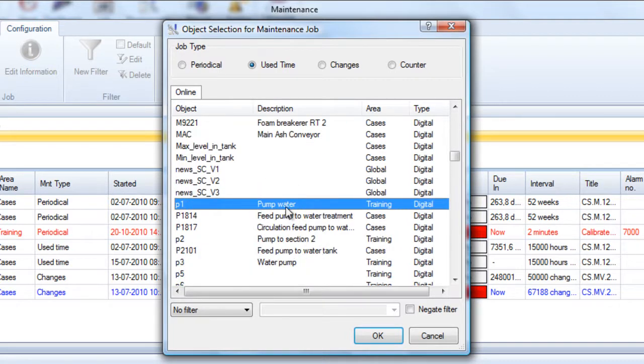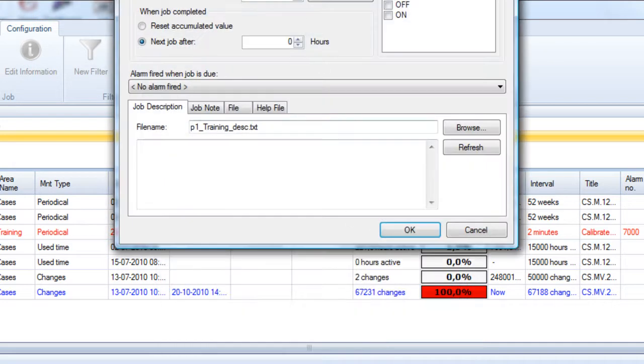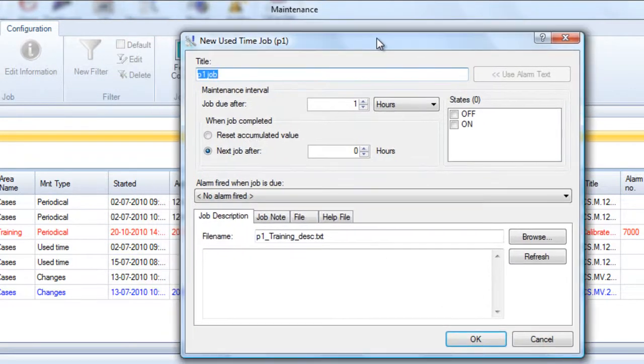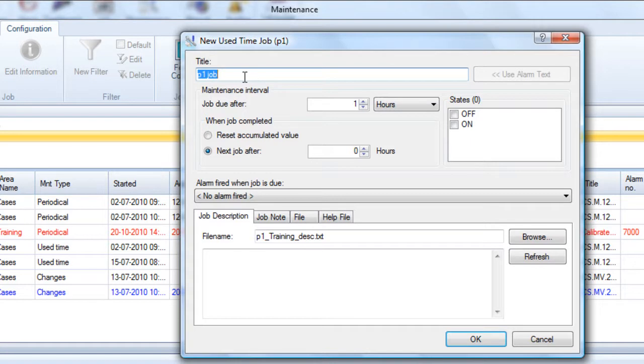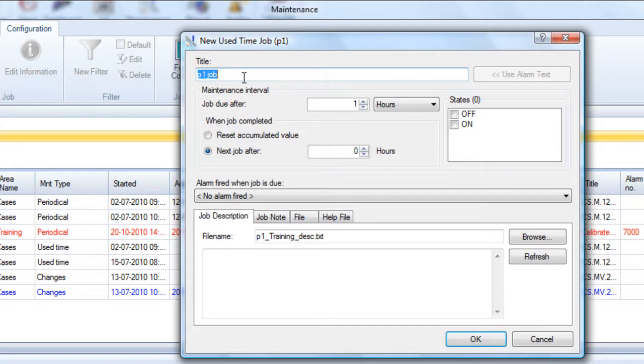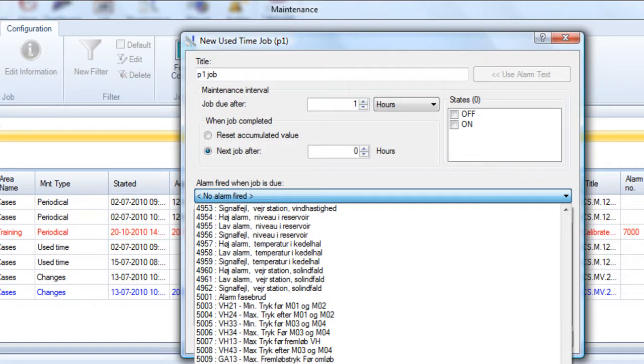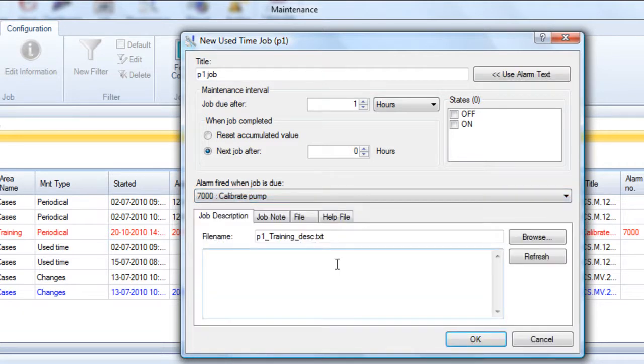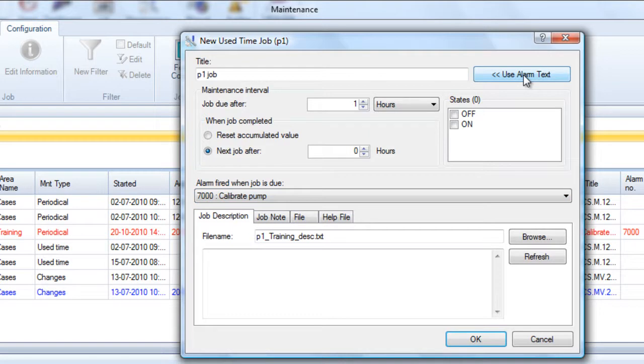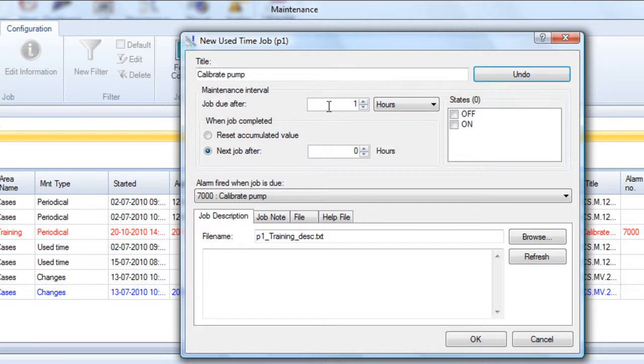Now first of all we have the title field. We can put in a title here directly in the dialog box, but what many of our customers will do is link an alarm text to this maintenance job, allowing the end user to see the maintenance job both in the maintenance list and in the alarm list. The linking is done here: alarm fired when job is due. We go down and select the very last one, 7000 calibrate pump. This is an alarm text that I've done in definition. I can click on use alarm text to insert that same text in the title field. So now we have the same name in the maintenance list and in the alarm list.